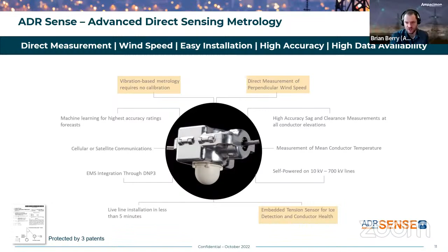And from sag, I can calculate the mean conductor temperature, not a spot temperature. You might think, oh, the best way to measure temperature, put a thermometer inside that box. No, that's just going to measure one little hotspot at one little location. That's not what I need. I need to know the temperature of that entire line. Okay, so this gives me the sag measurement, gives me a much better measurement of the temperature across the entire line. I also measure the vibrations, and those vibrations, which we'll talk about, give me a way of measuring speed very, very accurately. And all of this feeds into dynamic line rating.